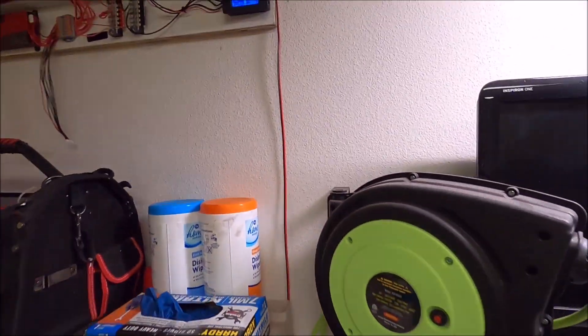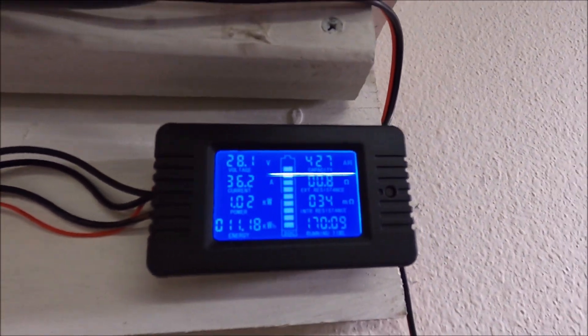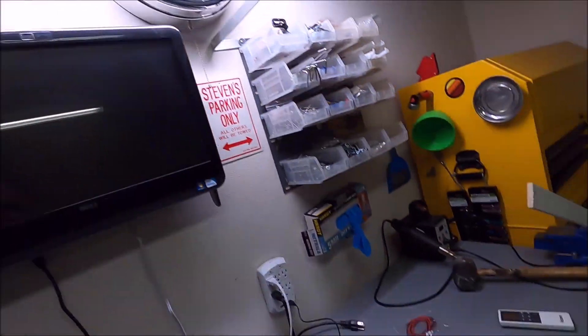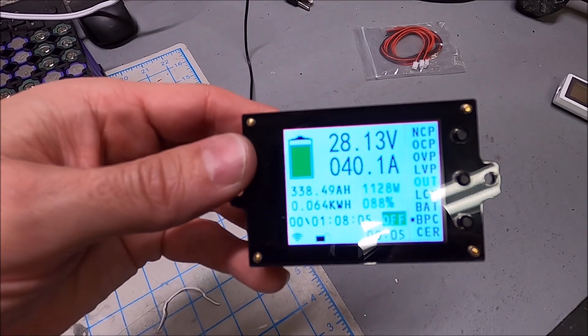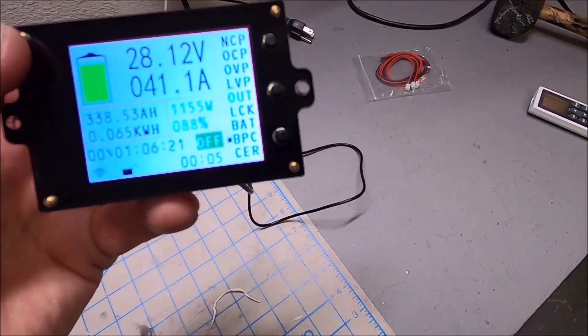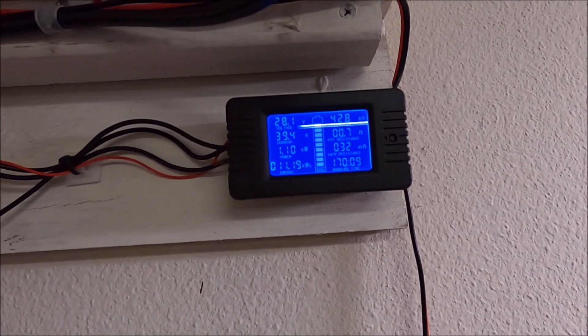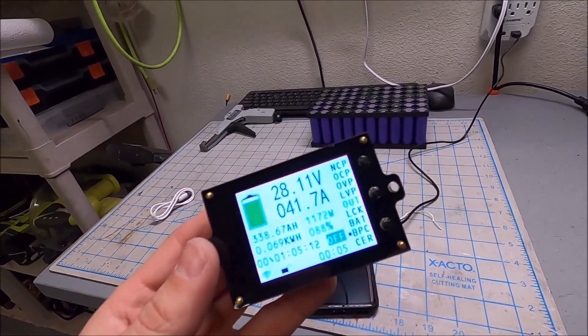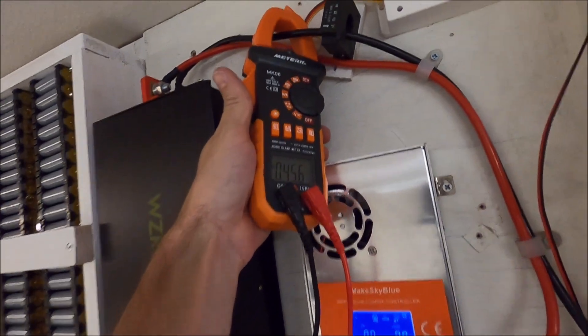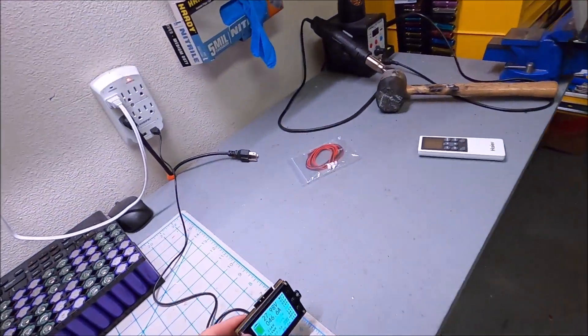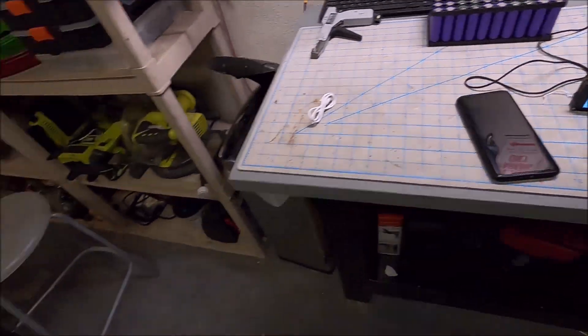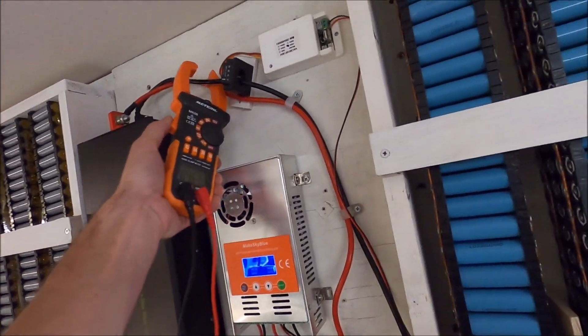This meter is showing 36 amps. And this is showing 30, well, it's rising. So this is saying 40 amps right now, 41 amps, 39 amps. So there's about a two amp difference, not too bad. Let's check the amps here. That is showing right now 45 amps. This is showing 46 amps. So pretty accurate, maybe within one amp. I'm pretty happy with that.